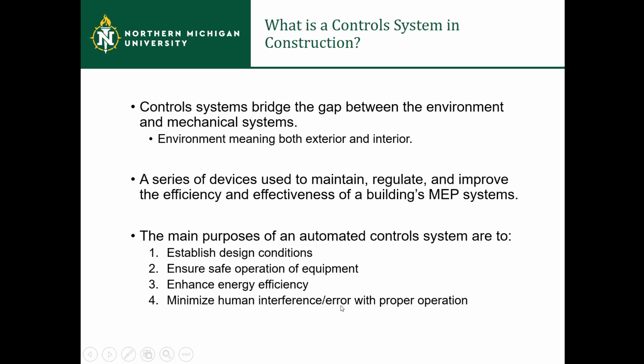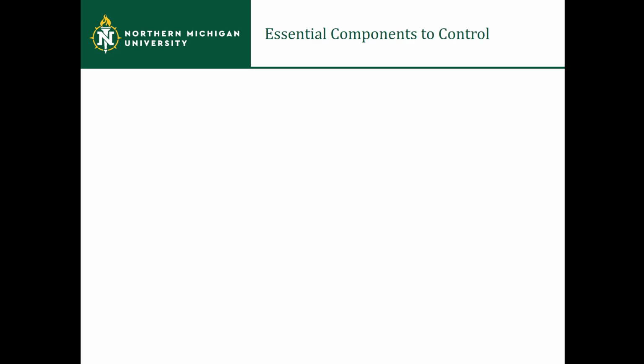As you build more large commercial operations or facilities, we have thermostats on the wall, for instance, which are part of your control system. A lot of people like to go mess with those thermostats, making things hotter or colder in spaces. In reality, there are set points behind them. Even if you bump it up to like 75, it's probably only going to go up to about 71 or 72, because if we allow everyone individual control over different spaces, the mechanical systems won't operate the way they need to. So even though it may say 75, if that building's only designed to operate at 72 max with the set point, that's probably as far as it will go.